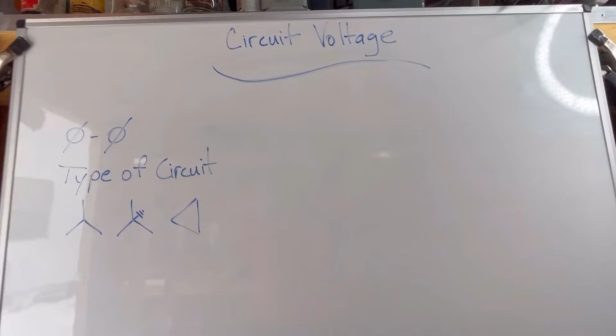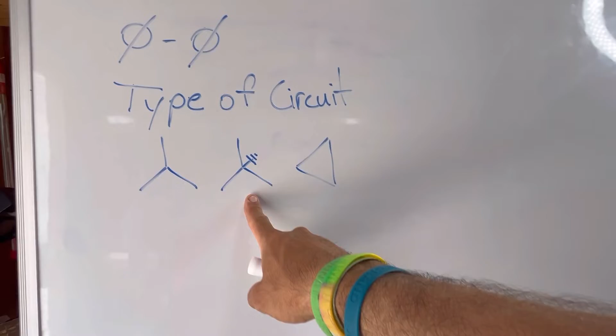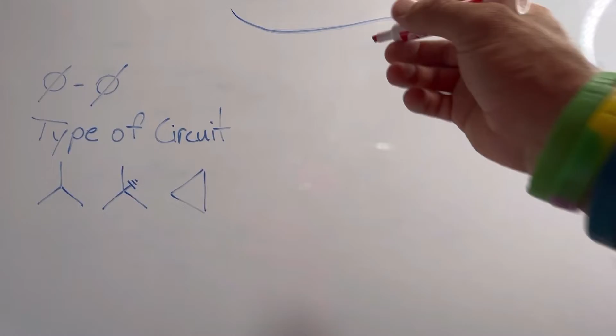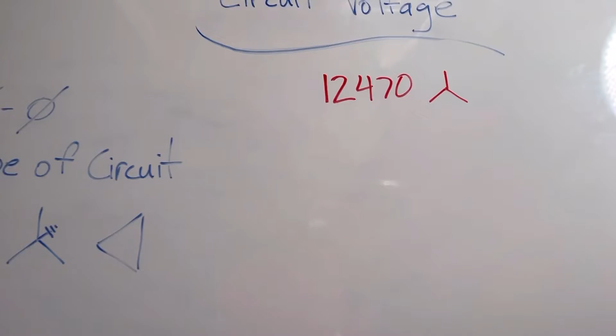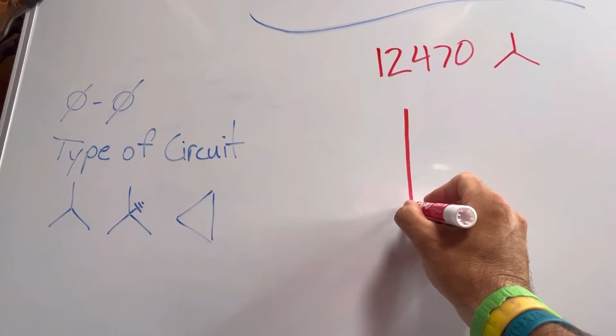All right, guys, so now we're going to talk about circuit voltage. What I'm talking about when I talk about circuit voltage is the phase-to-phase potential of that circuit and the type of circuit it is: a Y, a grounded Y, where the neutral is bonded to ground potential, or a delta. All right, guys, so the first circuit that we're going to talk about, I'm going to say this circuit is a 12470 Y circuit. So 12470 Y. What that consists of are 3 phases and a neutral.